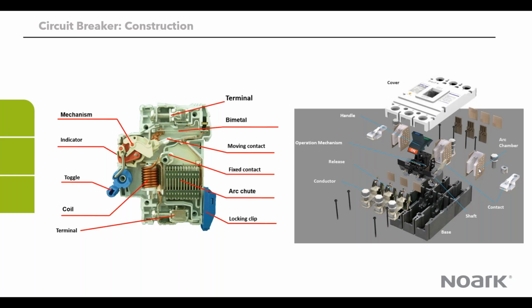So the arc chamber is where the arcs are formed whenever the breaker is trying to open the contact, whether in the normal situation or an abnormal condition. You're gonna have what we call an arc. Basically, when the contacts are trying to separate, because of the voltage and the current involved, the current will still want to continue flowing, but the contacts are already separated. So it's going to try to flow through the air, basically ionize the air and turn it into a conducting path, and that process is what forms what we call the arc. It can generate a substantial amount of energy, and so that energy needs to be dissipated.